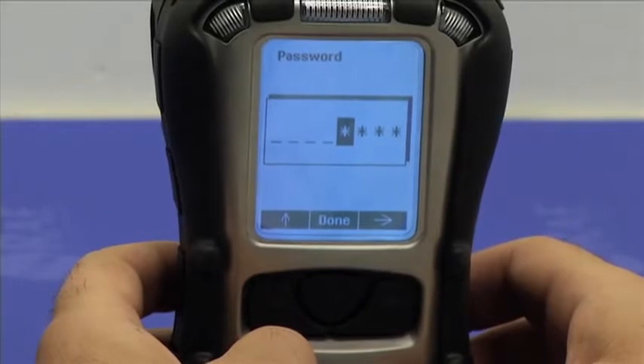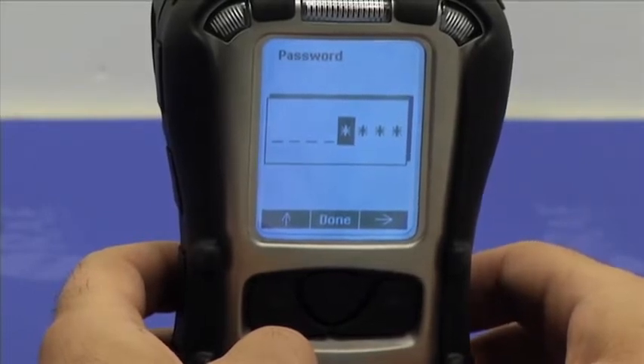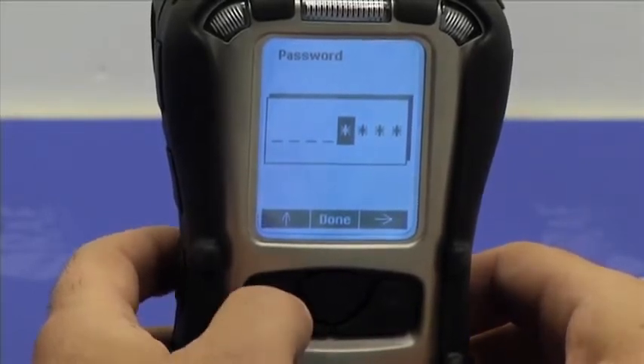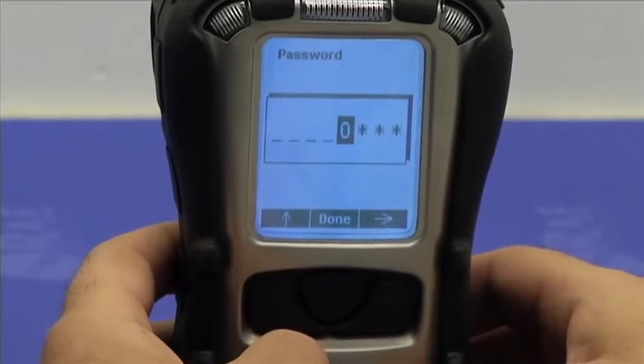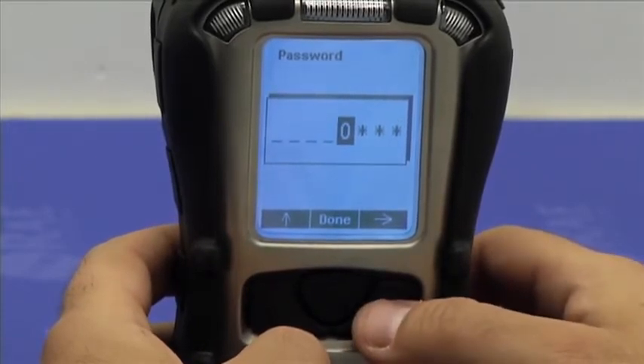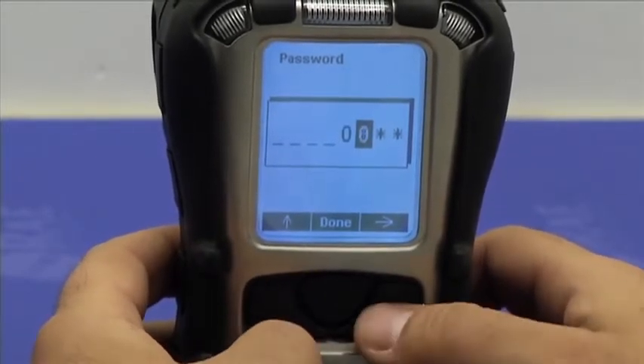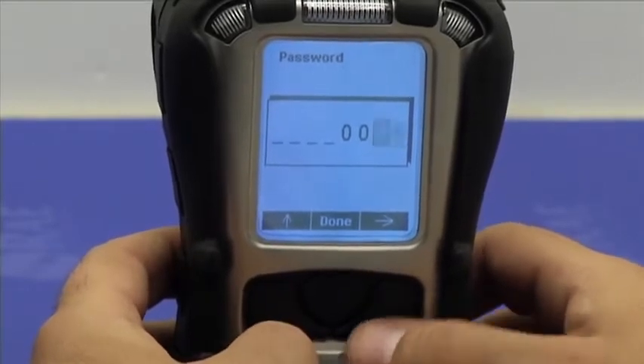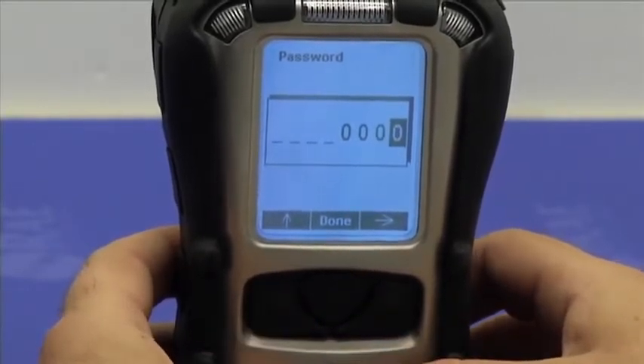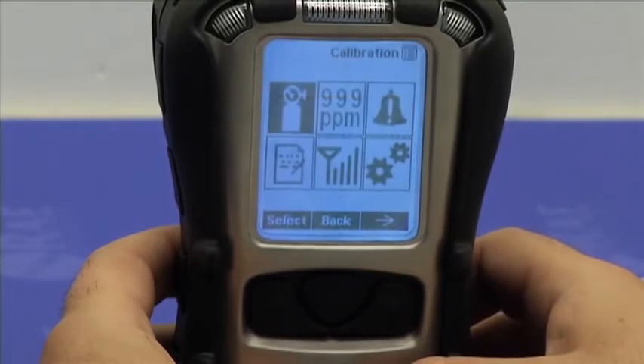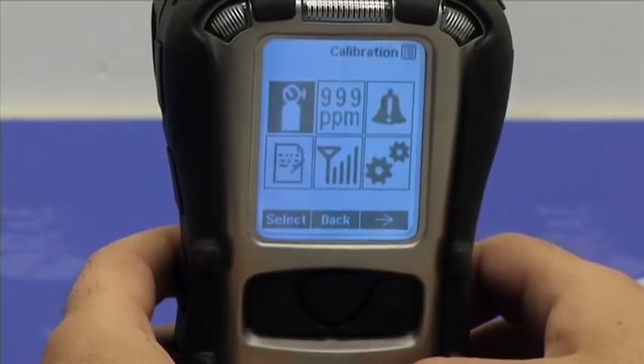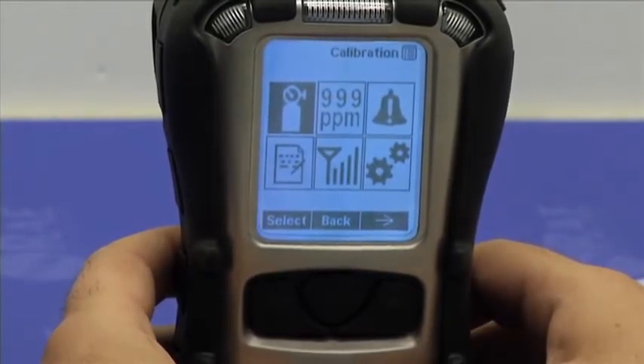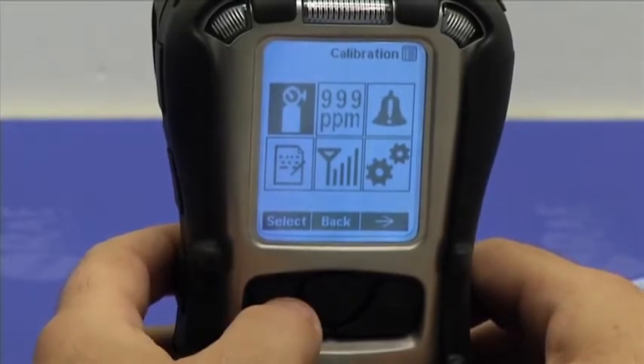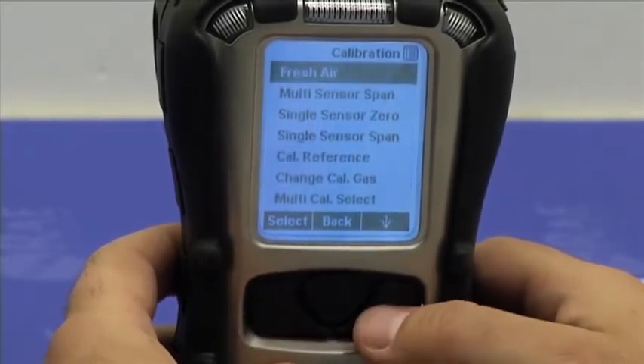If I do know the password, and the default password is 0000, I would enter it by pressing the Y button, followed by the N button to advance to the next character. So I would enter the 4 zeros, and then when done, I would press the Mode button. I'm now taken to the full calibration and other menus. This is the programming screen. I would enter the calibration menu and go under multi-sensor span.